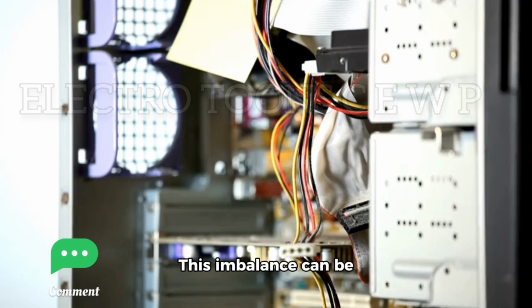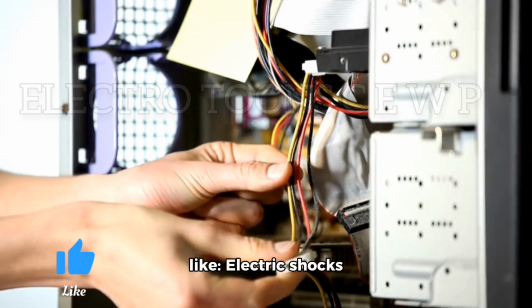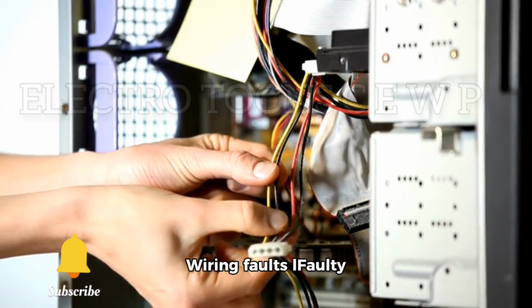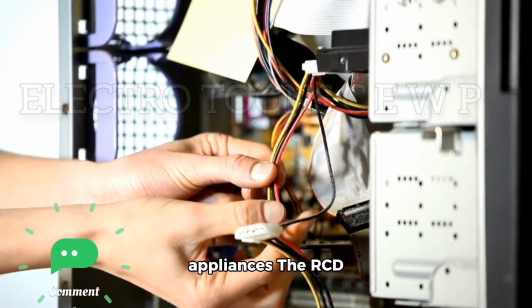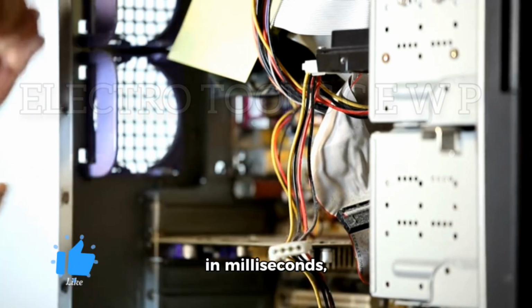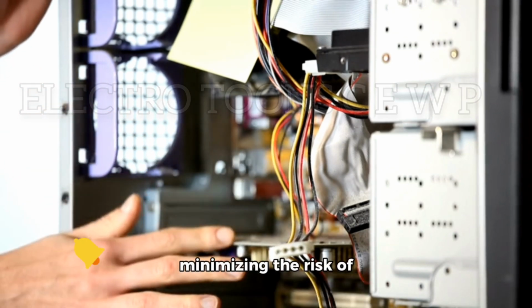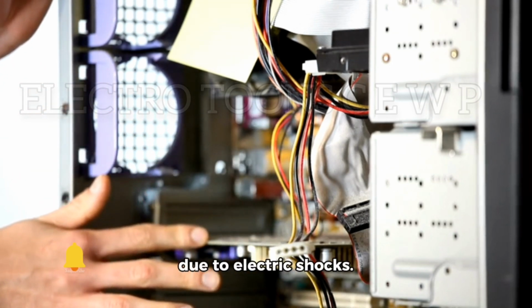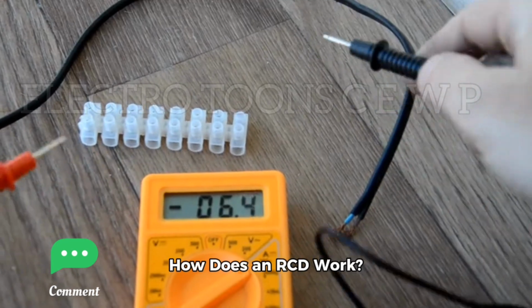This imbalance can be caused by situations like electric shocks, wiring faults, or faulty appliances. The RCD typically cuts off power in milliseconds, minimizing the risk of severe injury or death due to electric shocks. How does an RCD work?